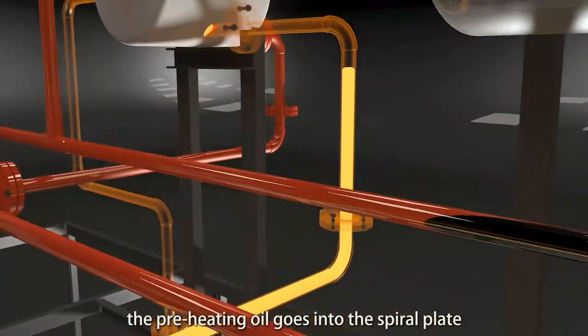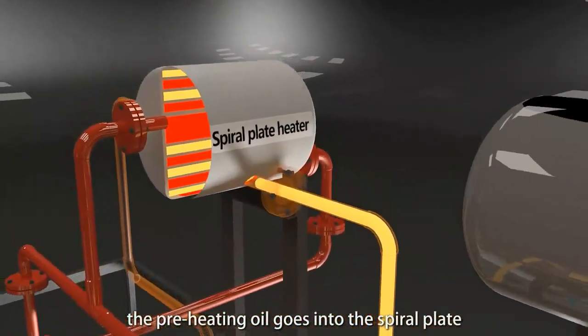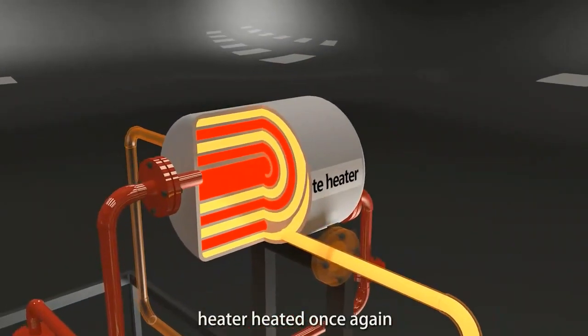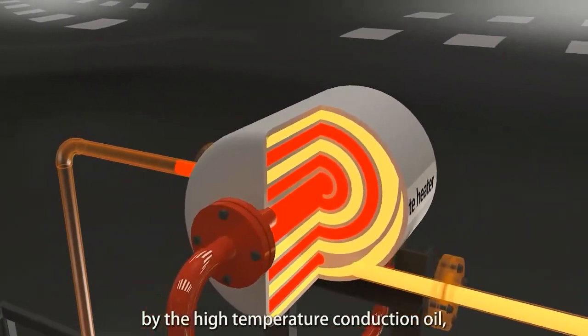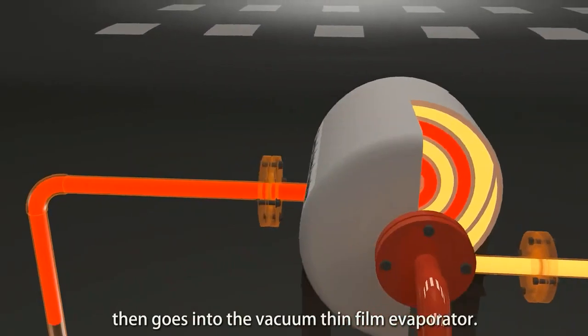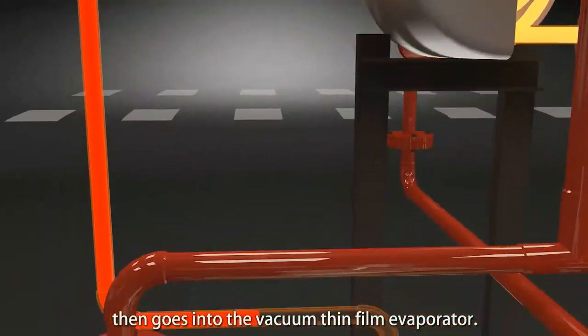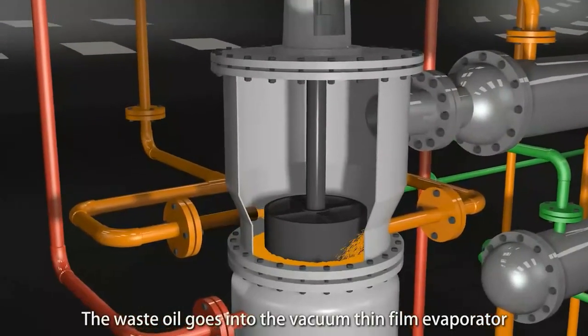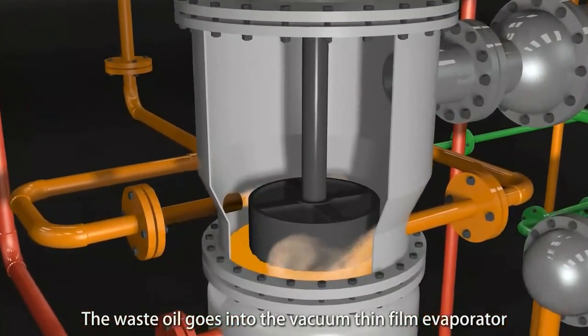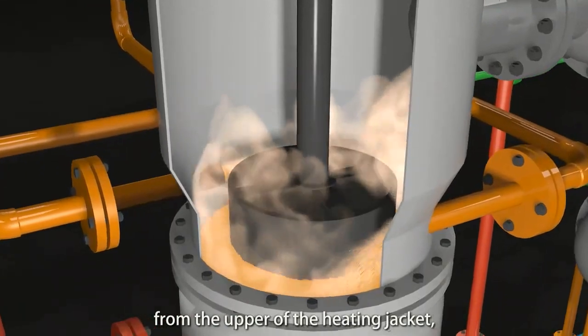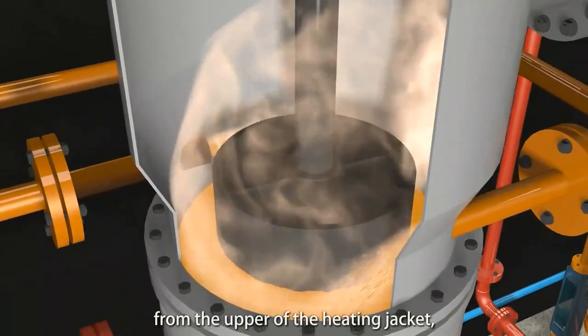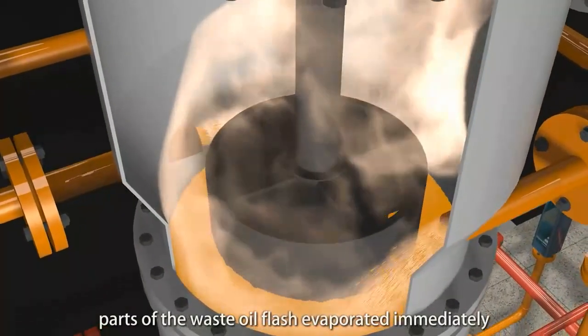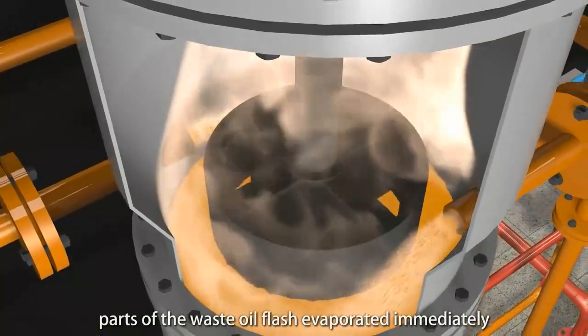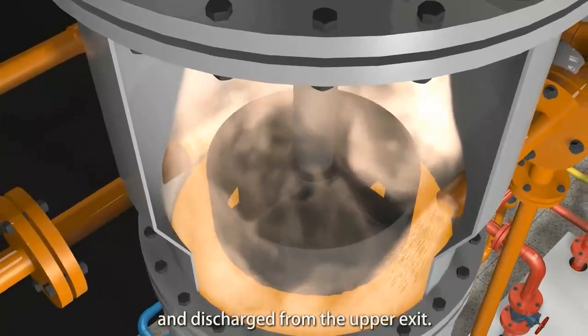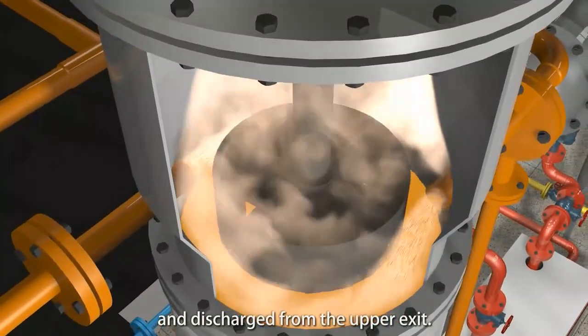The preheated oil goes into the spiral plate heater, is heated once again by the high temperature conduction oil, then goes into the vacuum thin film evaporator. The waste oil goes into the vacuum thin film evaporator from the upper part of the heating jacket. Part of the waste oil flash evaporates immediately and is discharged from the upper exit.